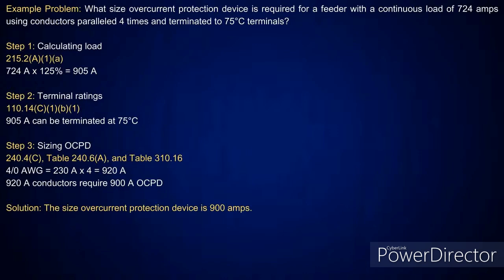Now I have to size the overcurrent protection device. Well, remember 240.4(B) deals with overcurrent devices 800 amps or less. 240.4(C) deals with overcurrent protection devices over 800 amps. Well, it says that the conductors have to be equal to or more than the size of the overcurrent device. So that means I have to drop down. And when you go look at Table 240.6(A), the next size below that will be 900 amps, but it's not listed. It's a non-standard type overcurrent protection device.